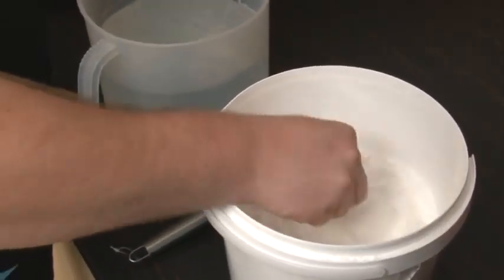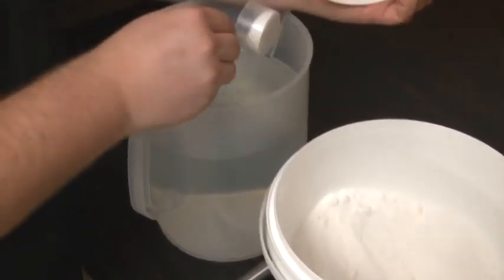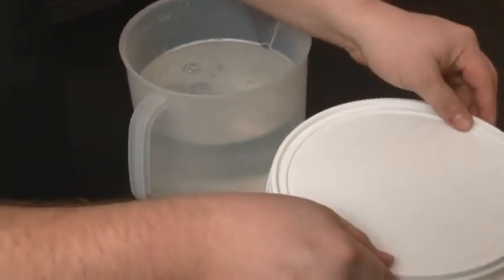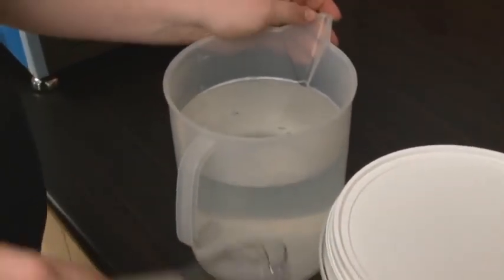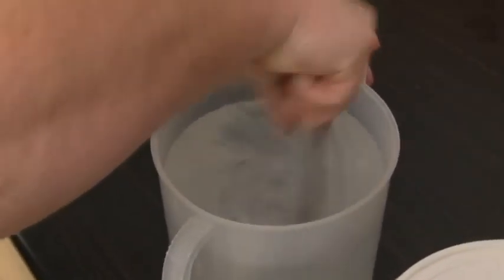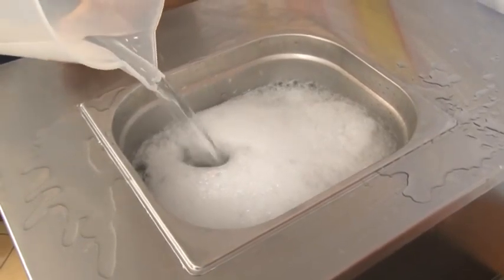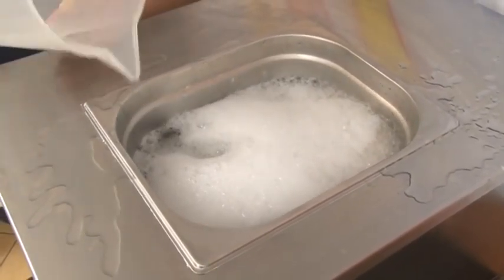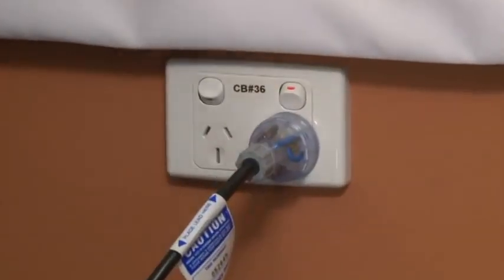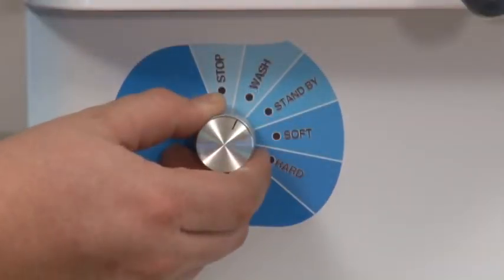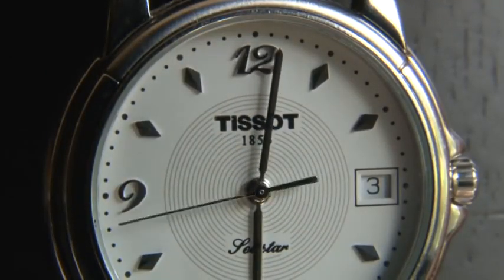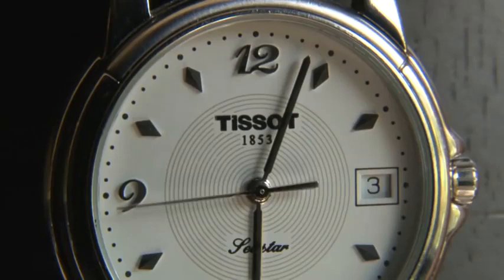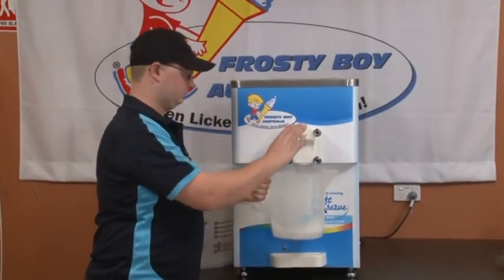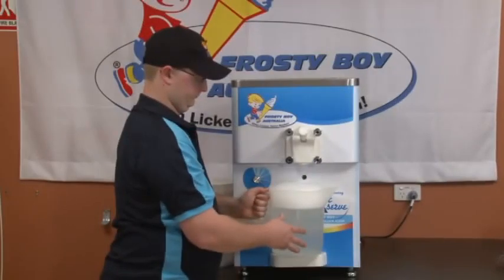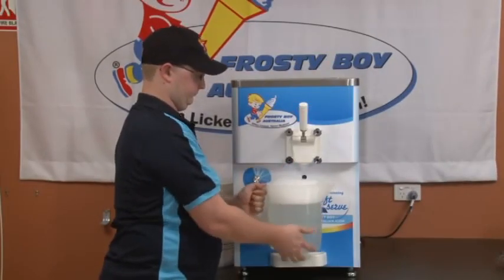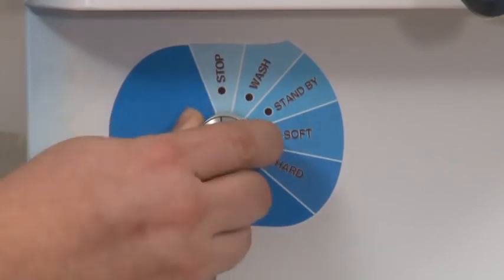Prepare about 5 litres of sanitizer solution as per the manufacturer's instructions and pour into the machine. Turn on the main power and switch the machine from off to wash. Allow the sanitizer to work for about 5 minutes. Drain the sanitizer and discard. Turn the machine off.